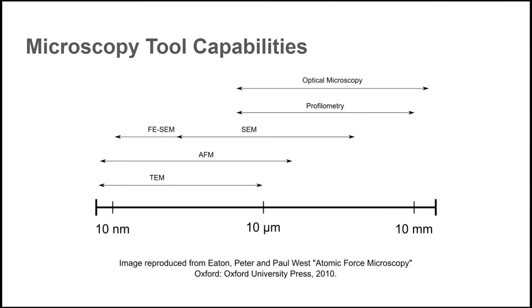Let's first orient AFM with other microscopy techniques. Depending on the lens, optical microscopes can resolve features perhaps as small as half a micron. Stylus-based profilers are limited by the size of the stylus, but typically resolve features in the 5 to 10 micron range. Thermal emission SEMs can resolve features down to approximately 100 nanometers, and field emission SEMs resolve down to 10 nanometers.